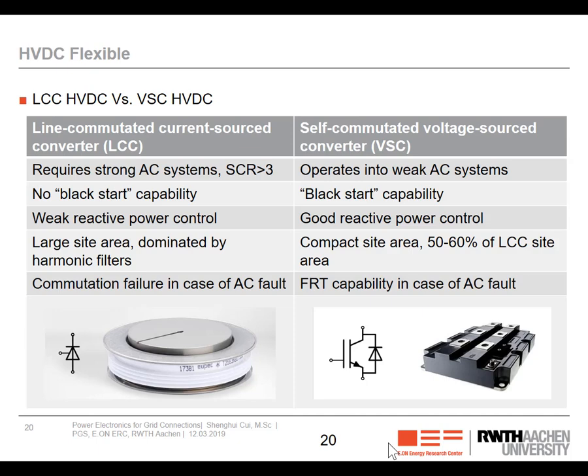It also lacks black start capability and has almost no reactive power control. It requires a very large site area for the converter stations, and for such a station, 2/3 of the site is occupied by the switchgear and the filters. Another problem is the risk of commutation failure in case of AC fault, because for thyristor converters, the commutation depends on the AC grid voltage. As soon as commutation failure happens, the entire transmission line can lose its power within several milliseconds.